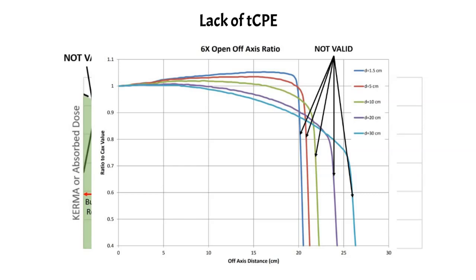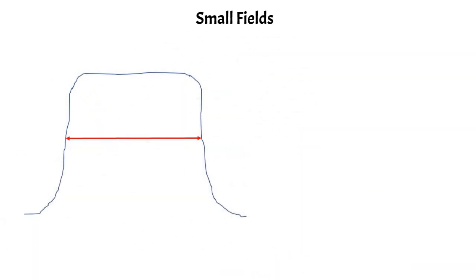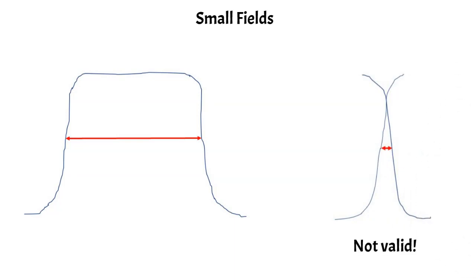With any hand calculation, it's crucial that charged particle equilibrium exists at the point of dose calculation. Extending the penumbra idea, this also applies to small fields. A regular-sized field has a sharp, well-defined penumbra, but as the jaws are brought in and the field size decreases, eventually the penumbras on each side overlap. Since the penumbras are overlapping, there is no point of charged particle equilibrium within that field. For very small fields, the hand calculation formalism is not valid because CPE conditions do not exist.